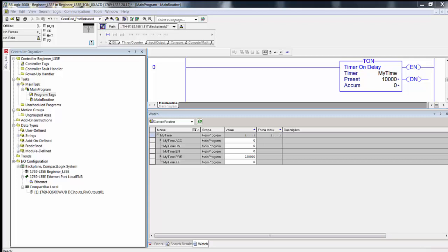The original intent of this instruction was to delay the on state of a bit in memory for the length of the timer's preset, delay on, after initiating conditions were true or after an event occurred. Originally, these were relay timers, and when you energized the initiate or start input or screw terminal on this timer relay, it started a timer, and you would set the timer in the older ones with a little knob on front, and it was not very accurate.